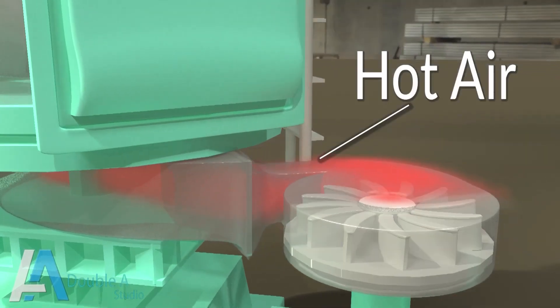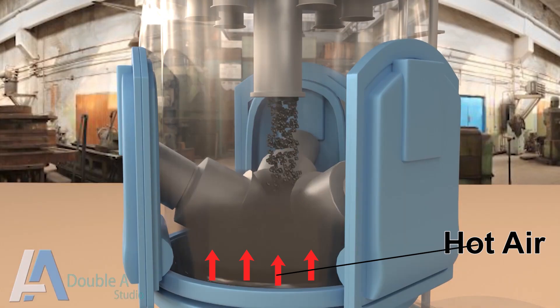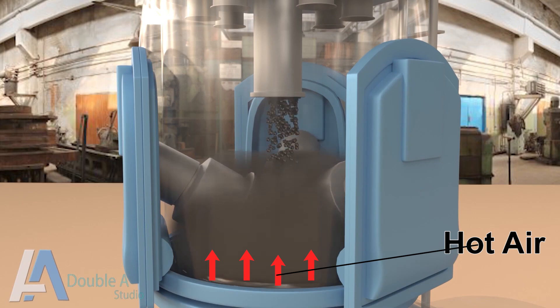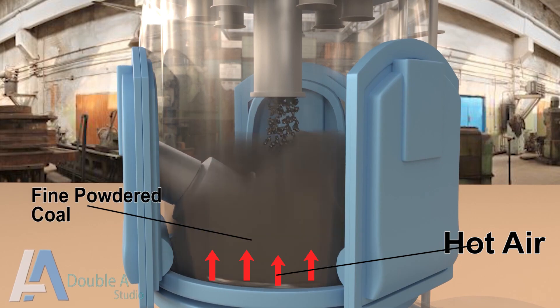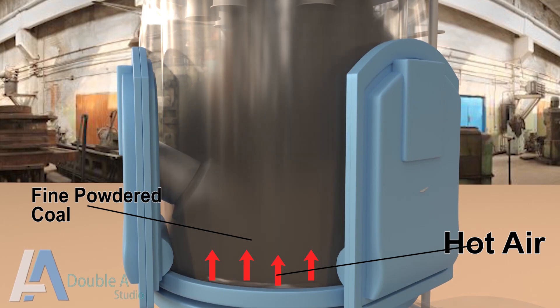To facilitate the flow of hot air, PA fans are installed at the bottom of the mill. They create positive pressure and throw hot air inside the mill. When hot air enters the mill with pressure, it carries fine powdered coal with it and sends it to the boiler. As a result, coarse coal falls back for pulverization and the process repeats.